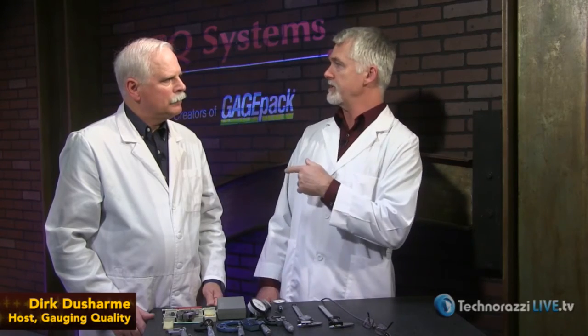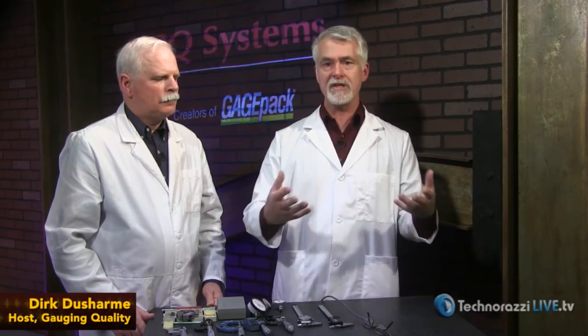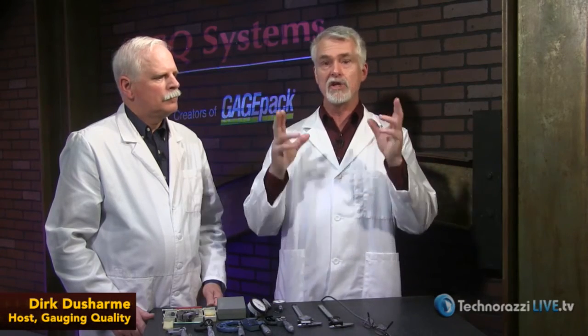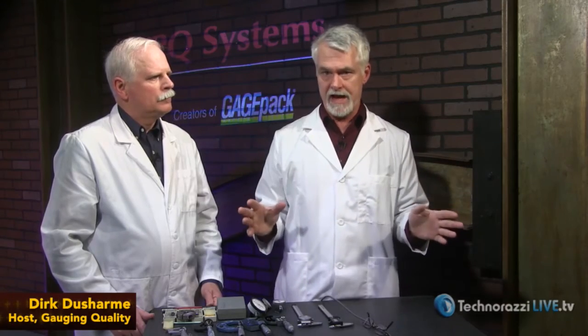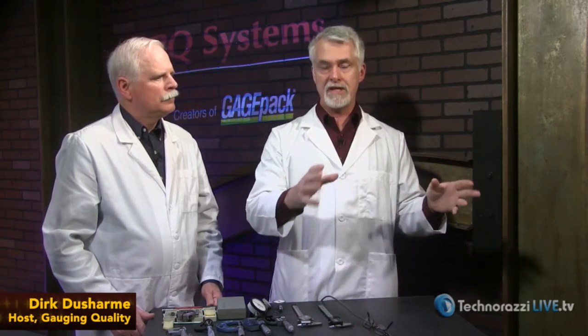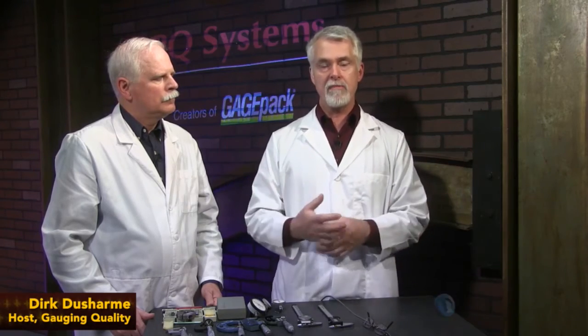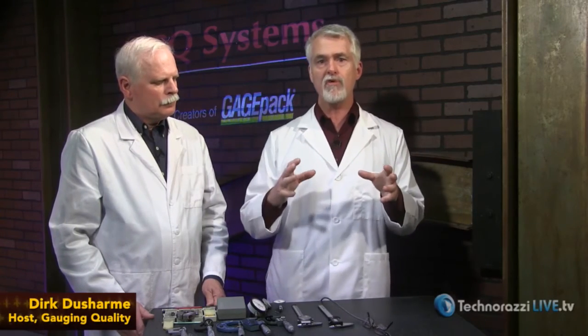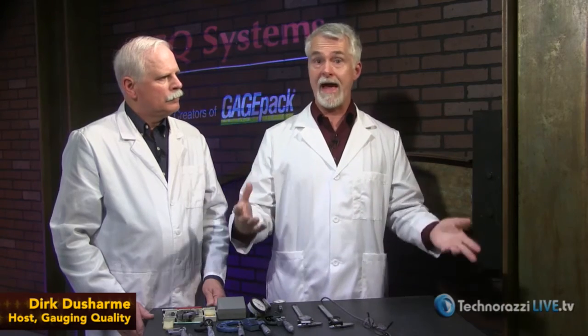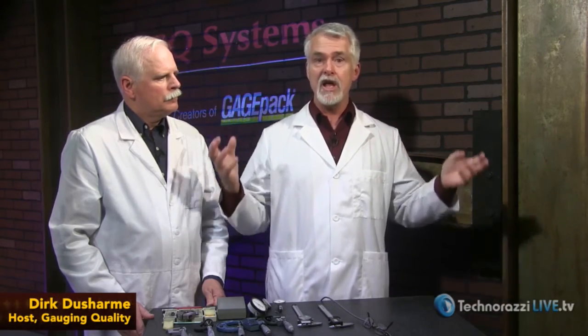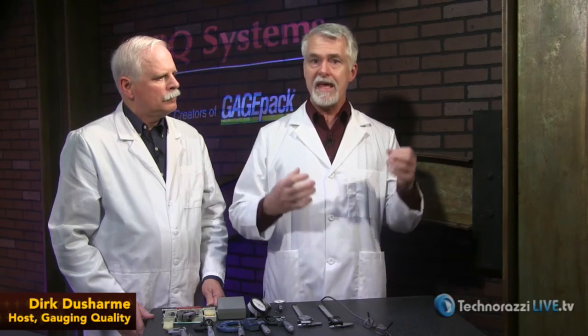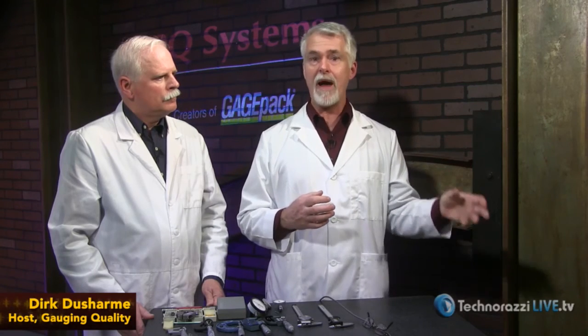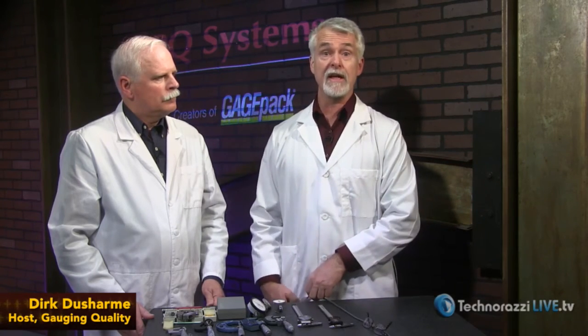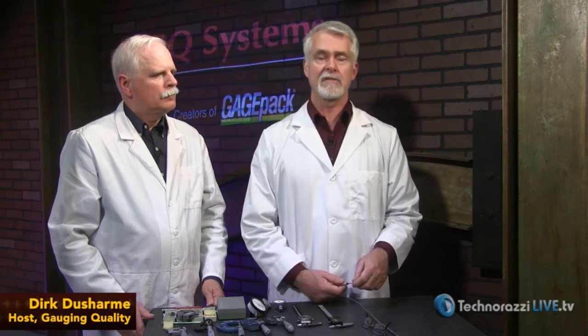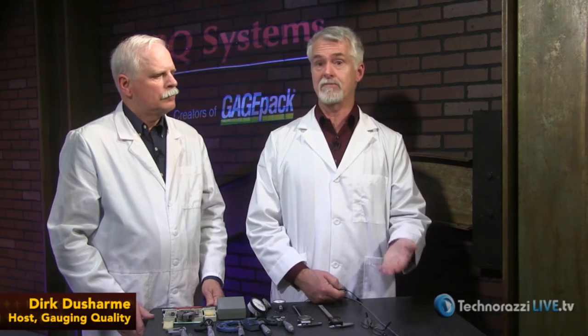So basically, proficiency testing interlaboratory comparisons are sometimes called a round robin. Essentially, a golden part is sent out to several different labs. All of the labs take measurements on that golden part and report their measurements back to whoever's coordinating the study, the director of the study. Ideally, all well-run labs, all labs that are doing their job properly, should come back with basically the same results. If the director of the study sees that a lab is out of whack, then they need to look into it and find out why. Is it something to do with the environment? Is it something to do with personnel training? Maybe they've had some personnel turnover.